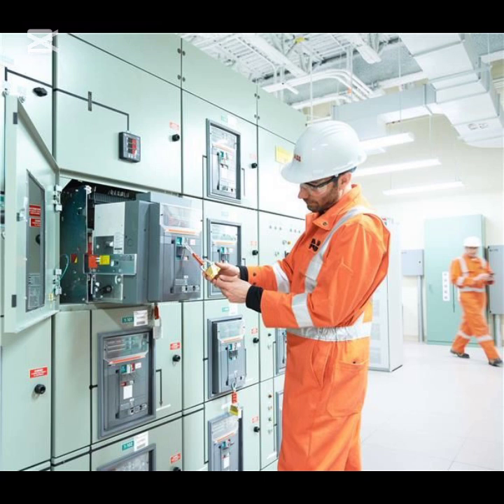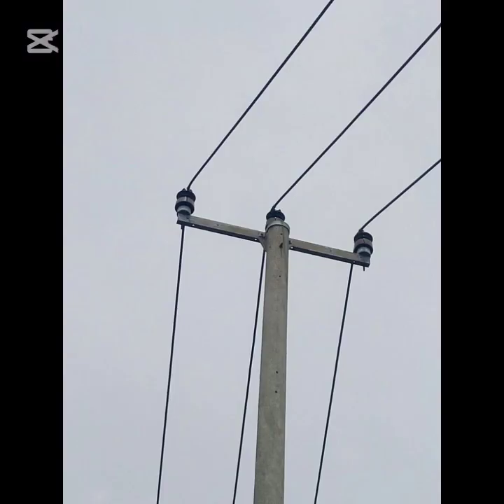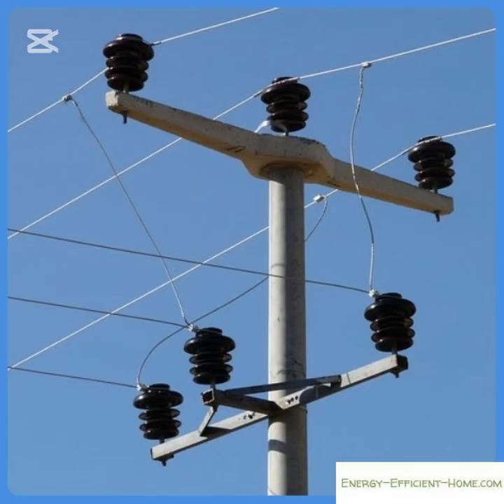Let's explain each insulator one after the other. One: pin type insulators. As implied by their name, these insulators are attached to the cross arm on the pole. They have a groove at their upper end for holding the conductor. The conductor is tied in the groove with an annealed wire made of the same material as the conductor. Pin type insulators are suitable for electric power transmission and distribution at voltages up to 33 kilovolts, but they become expensive and uneconomical for voltages above 33 kilovolts.